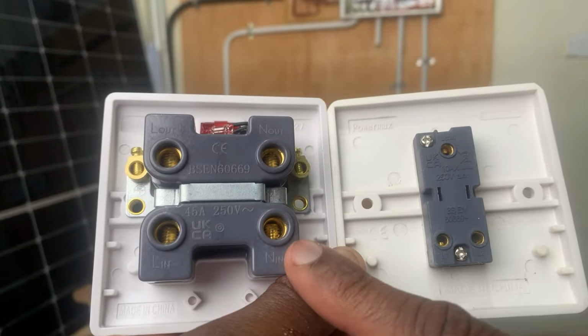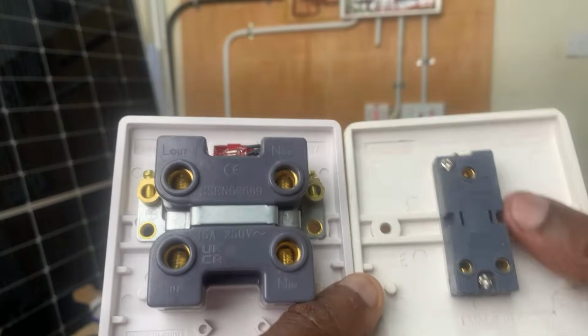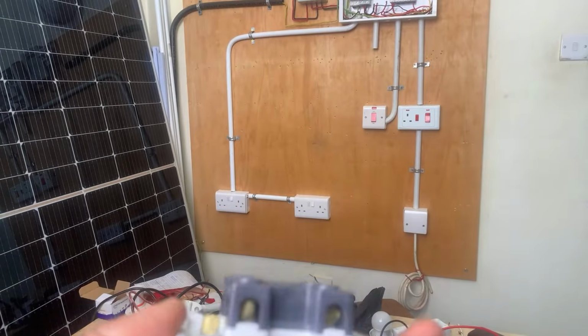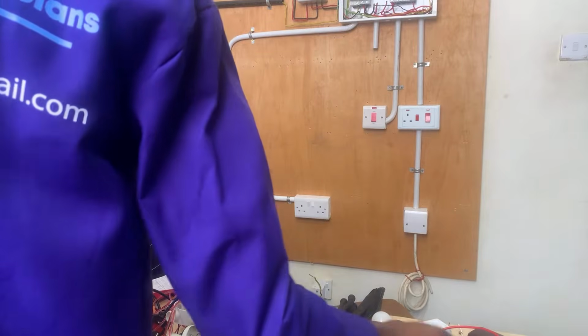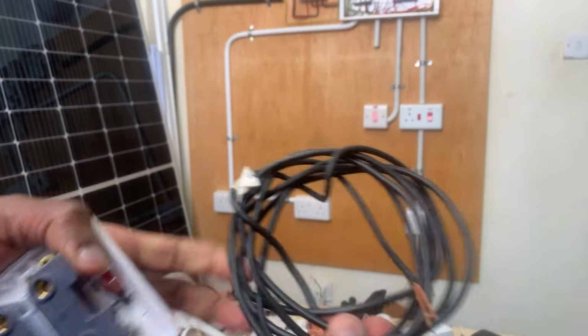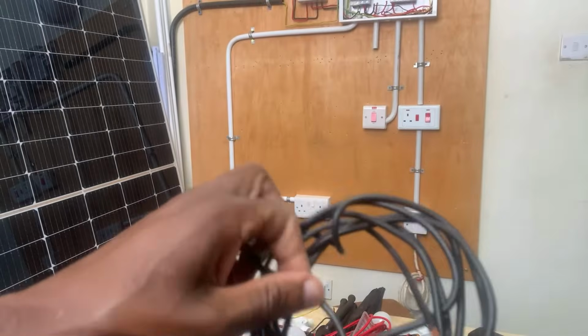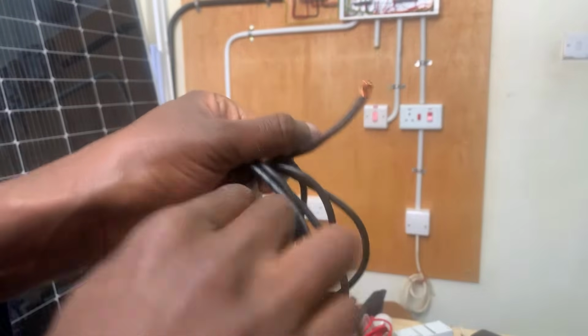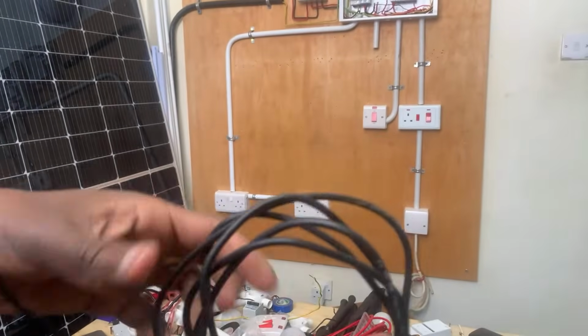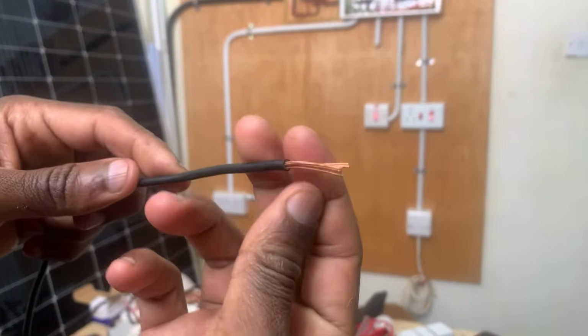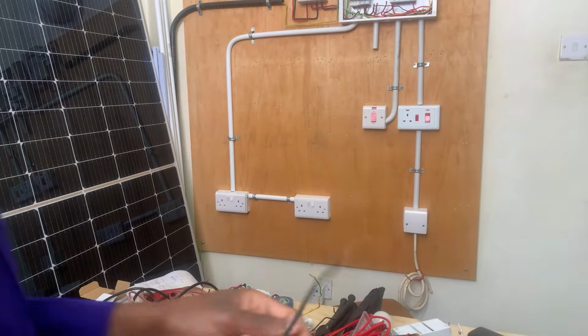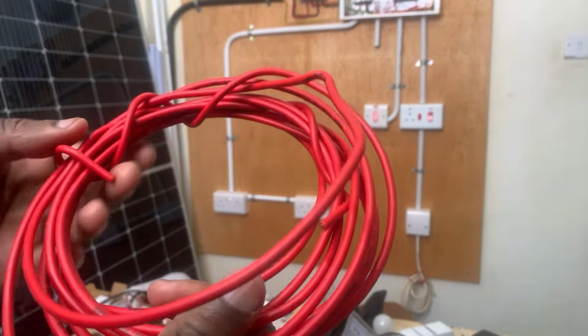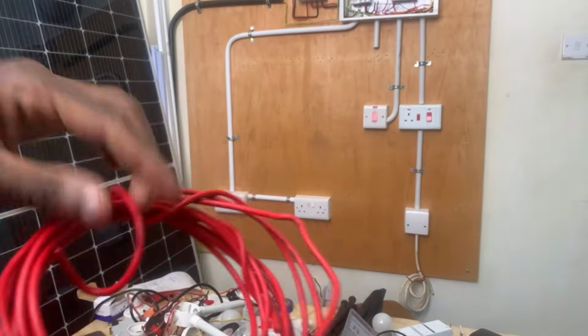So with this switch, mistake number one is that people don't tighten the screws. If someone is wiring a cable, let's go right into it. Let's say we have a 4.0 cable—this is our cable. In most cases this circuit is wired with a 4.0 or 6.0 mm cable, that being the cross-sectional area of the conductor. This is what we have, and also taking the phase, which in our case is a red cable.